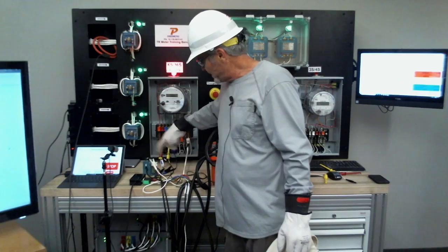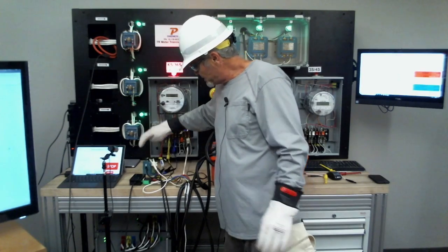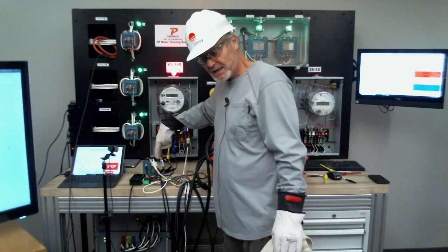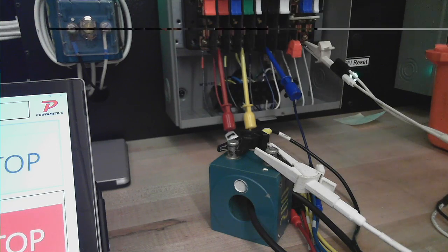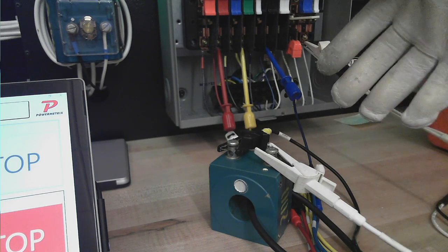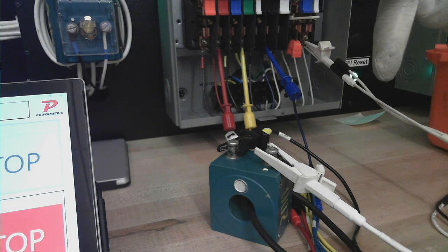Now over here, we've got just a straight flow in and out. All I'm doing is providing a primary current through that CT, and I want to measure the secondary side, then compare my primary to my secondary to get a ratio test and say, hey, is that a good CT? And I can green tag it and stick it on the shelf.